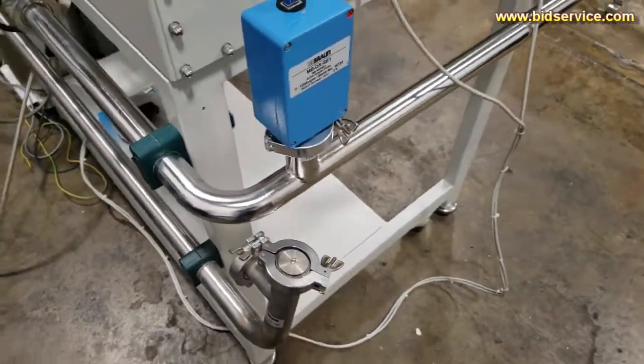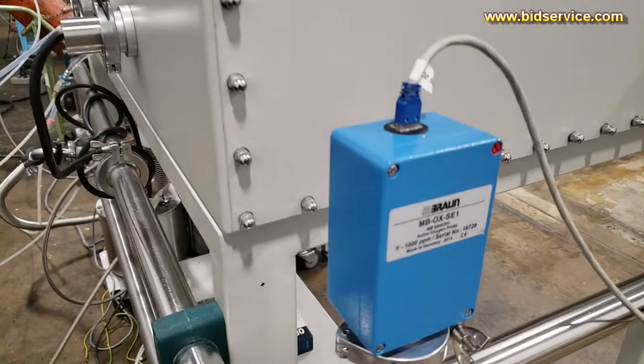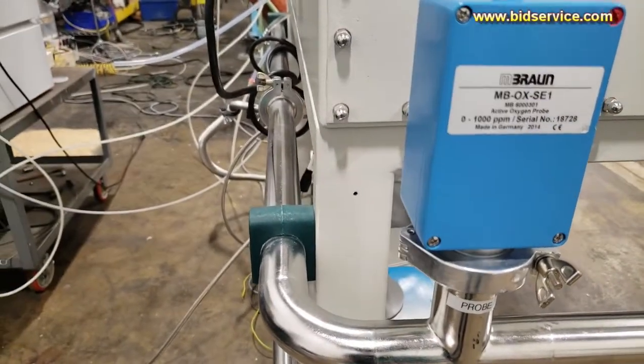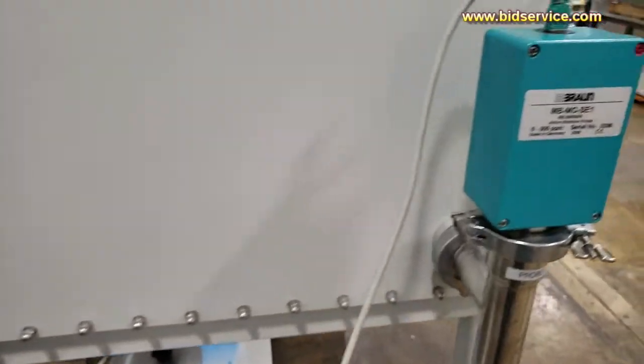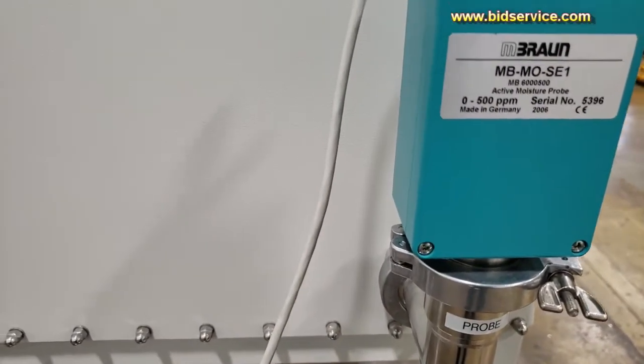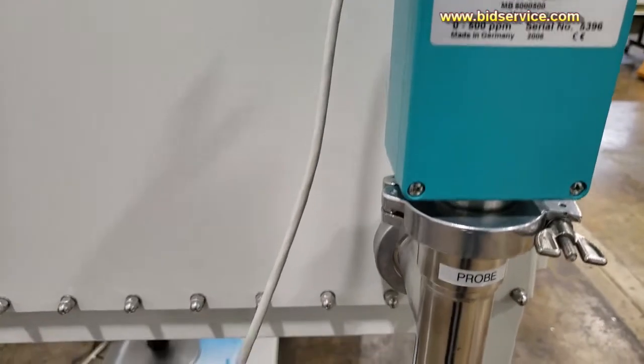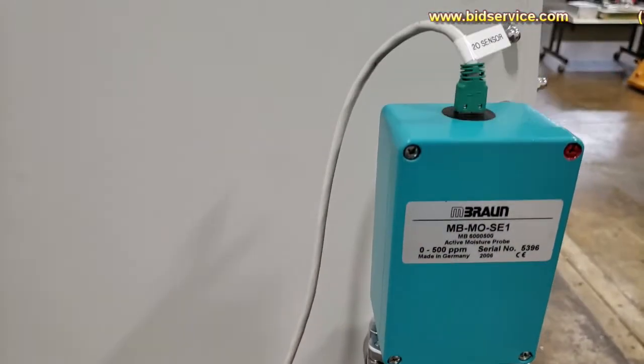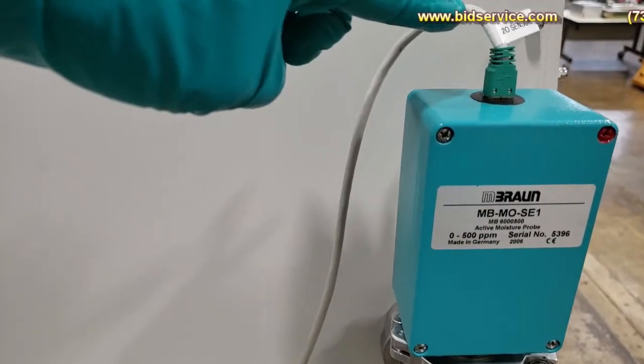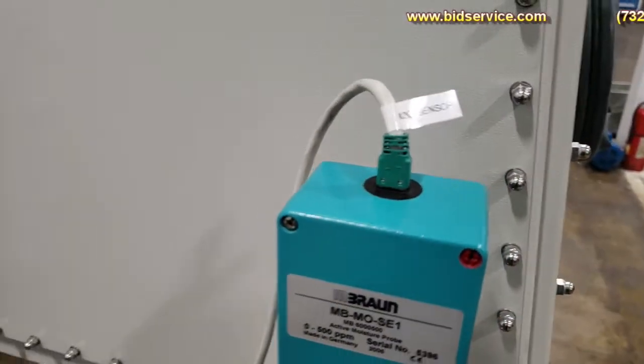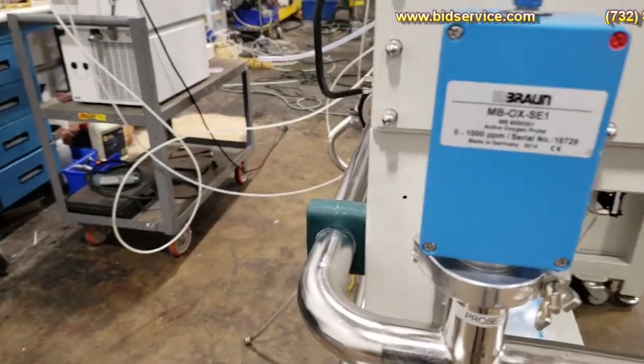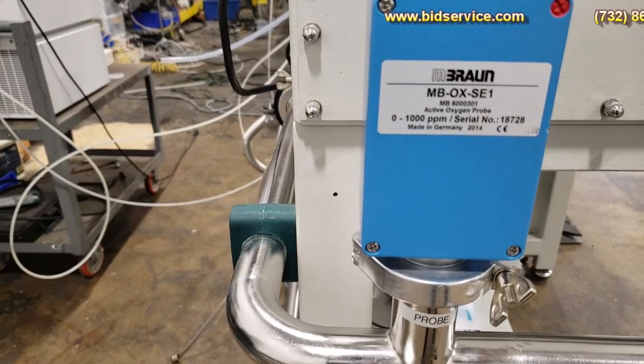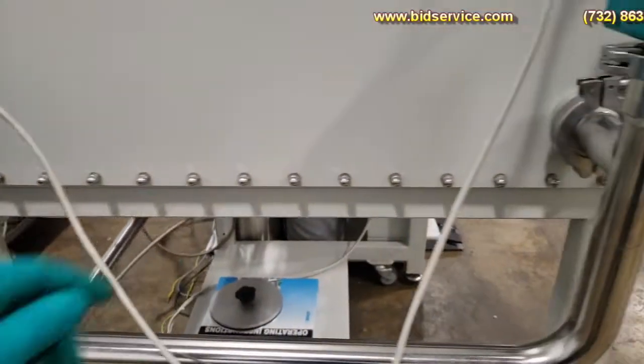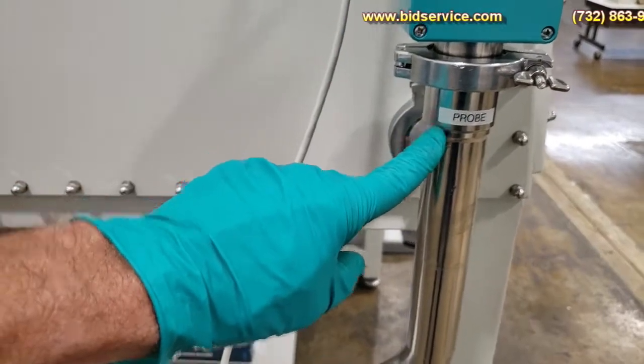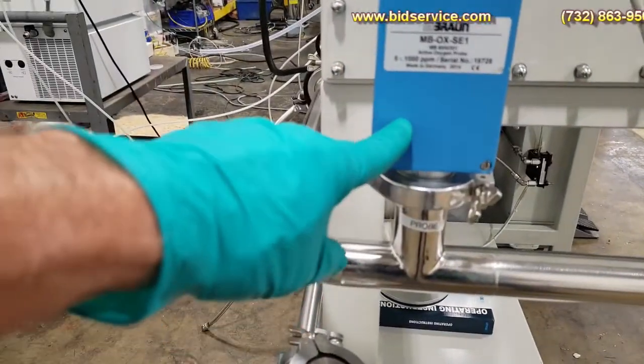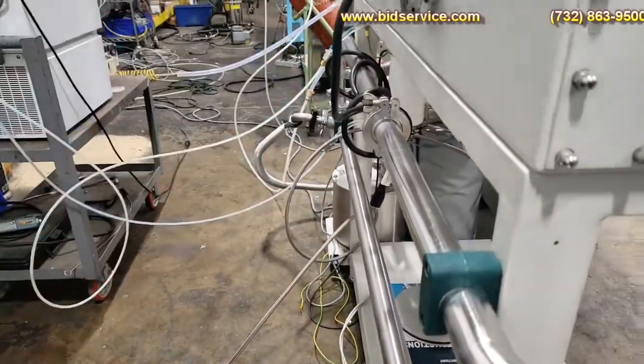I just want to point out while we're here that we do have our oxygen sensor and our moisture analyzer here. You see that's the moisture probe, the range 0 to 500 ppm for the moisture, connected with a green connection here, labeled H2O sensor. And then here's your oxygen sensor, 0 to 100 or 1000 ppm. So the return from the box is first across your moisture probe through this line, picked up by the oxygen sensor, and then right back to your purifier.